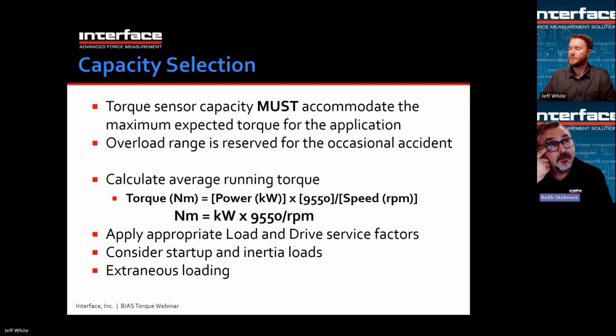They also have a safe overload range, and you want to reserve that safe overload for accidents. You never want to factor in using the safe overload as part of your measurement range. It's always designed for extra overhead safety factor in case of accidental loading above design intent.